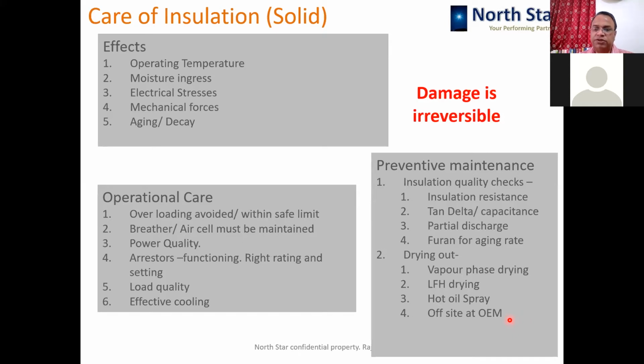So this dynamic situation of the moisture plays a vital role, and in most cases just filtration is not able to take the moisture out of the solid insulation. So drying out has to be considered from time to time. I'm not saying very frequently, but depending on the test results, you should go for drying out of the transformer. Many times people do filtration every year. That is not required most of the time, but it is still a practice in India and is being followed. But I don't recommend that, as it won't do much good to the transformer.